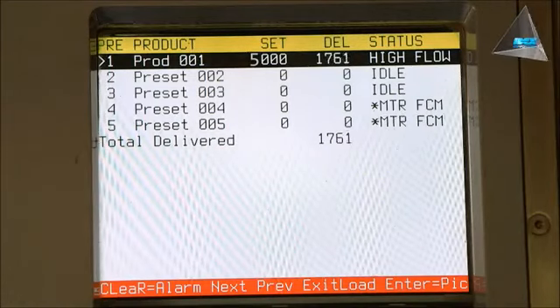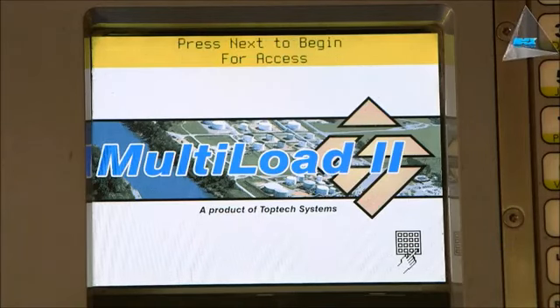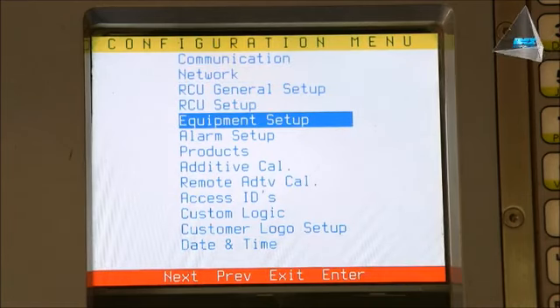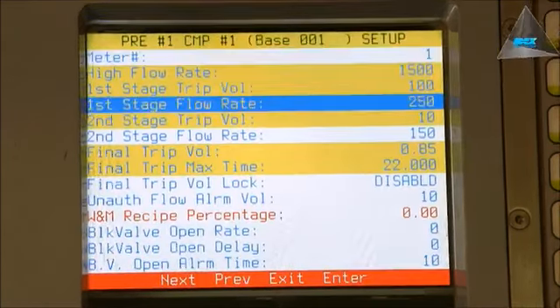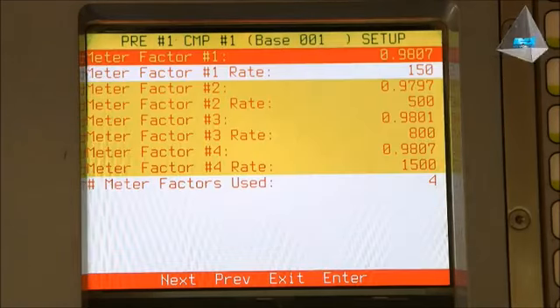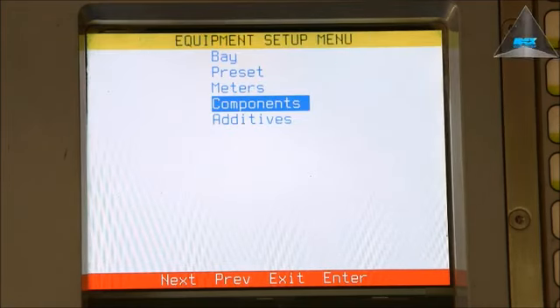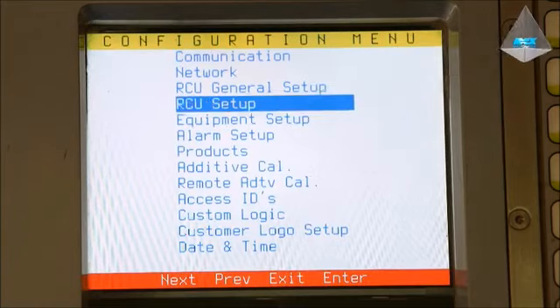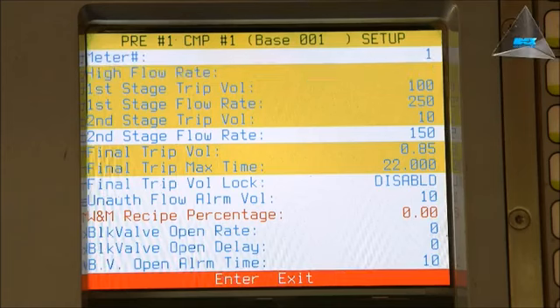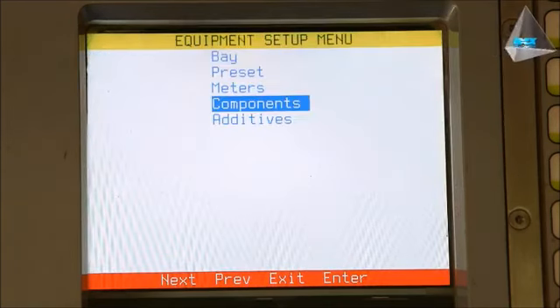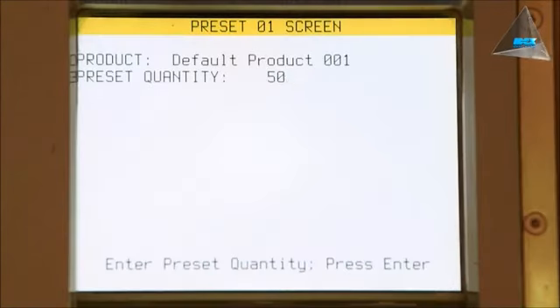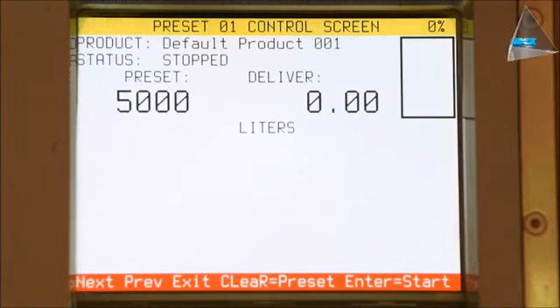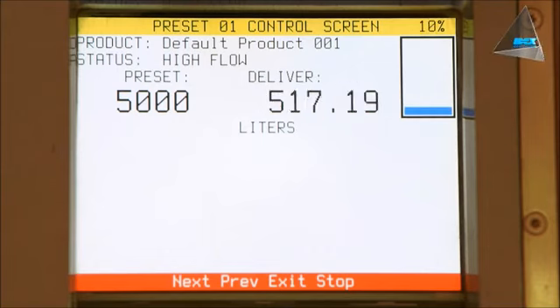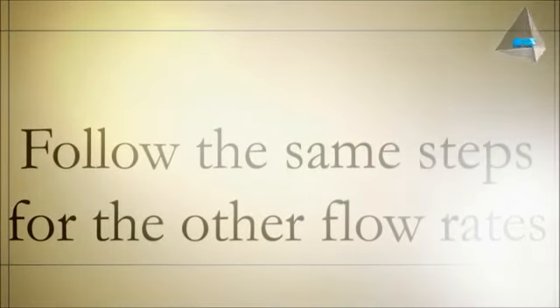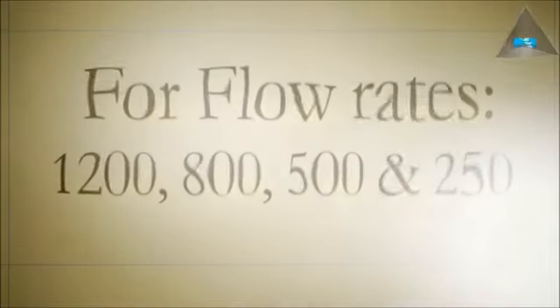Calculate the K factors from the prover and the meter readings for all the flow rates. Feed the master meter K factor data into the batch controller. Set the flow rate of 1500 LPM as required and the batch value of 5000 liters in the batch controller. Take 3 test runs and record the readings of the prover and the master meter at the end of each batch. Follow the same steps for the other 4 flow rates: 1200, 800, 500 and 250 LPM.